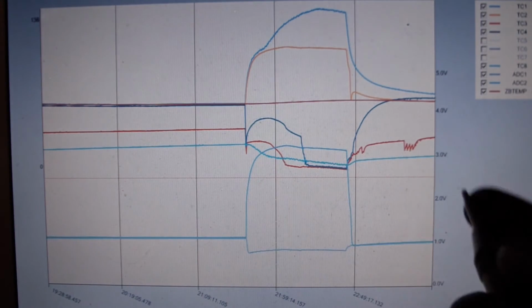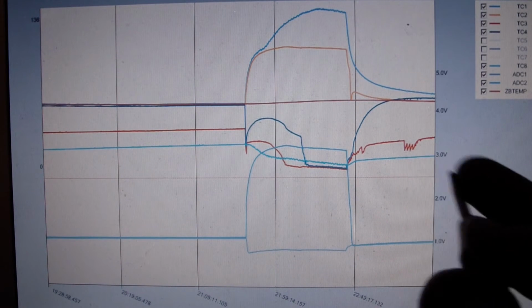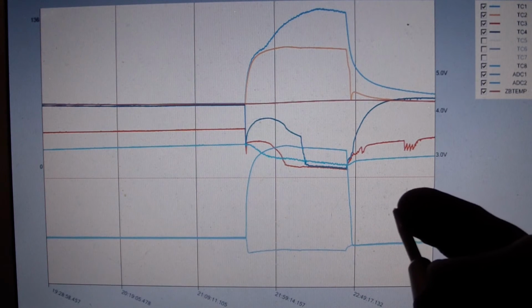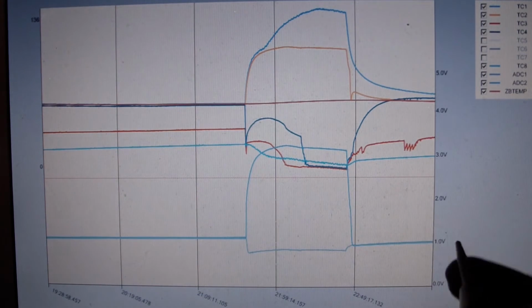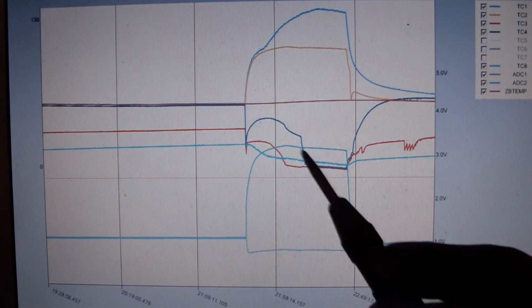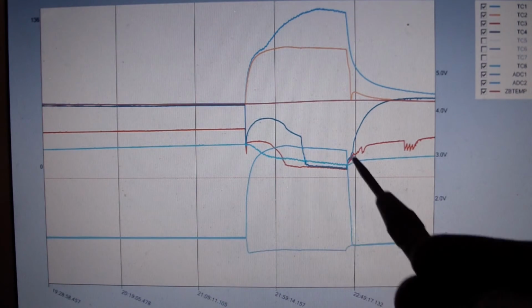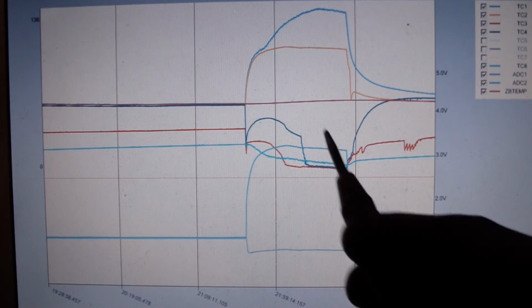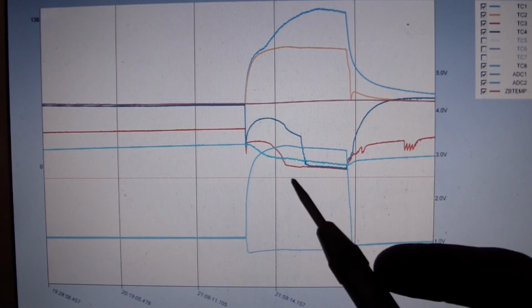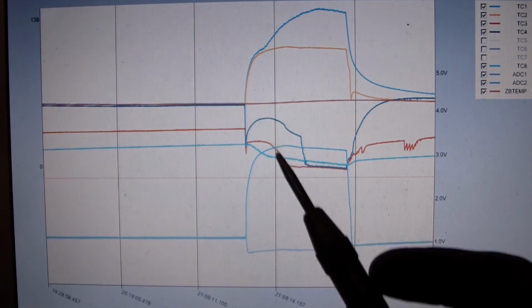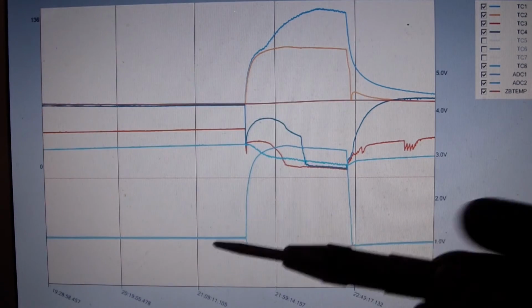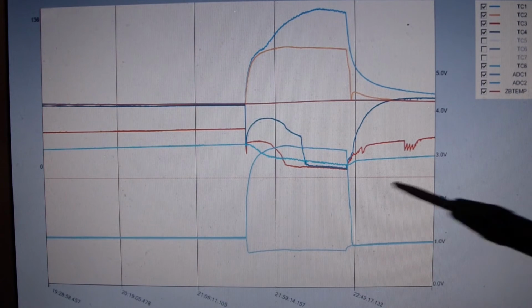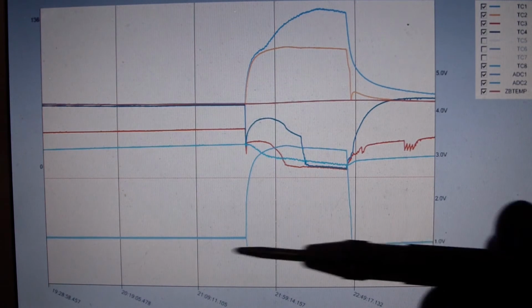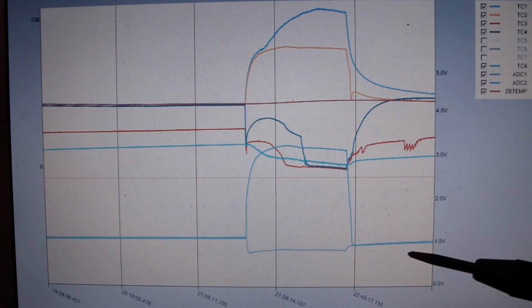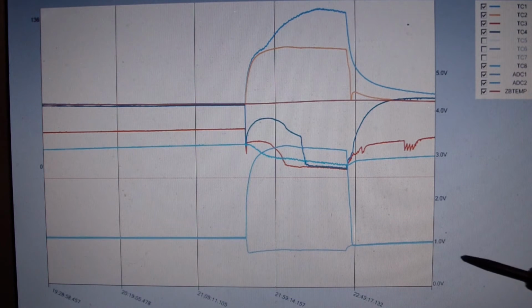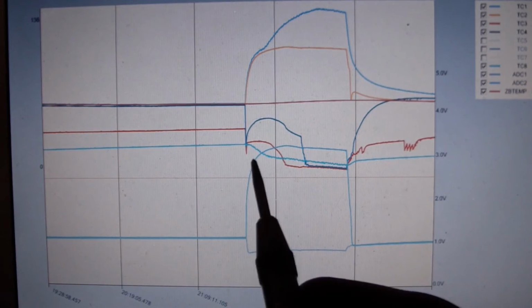I've dealt with accumulators a bit before. I don't know how well I was understanding the process, but over the course of the last few weeks, I've really been paying close attention, with the addition of some of the pressure information, trying to better understand exactly what's going on in every one of these cycles. To me, what the accumulator does after the evaporator is allow for some variation in system conditions. So depending on ambient temperature, maybe it's 60 degrees and cool in the room, maybe it's 90 degrees in the room, and then from the beginning of the cycle to the end of the cycle.